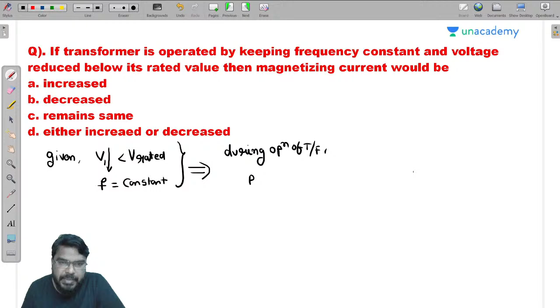By keeping frequency constant, if applied voltage is reduced, then the flux density of the transformer is reduced, so B maximum will be reduced. Decrease in flux density decreases the requirement of flux, and decrease in flux decreases the magnetizing component of the current. So the answer is option B.